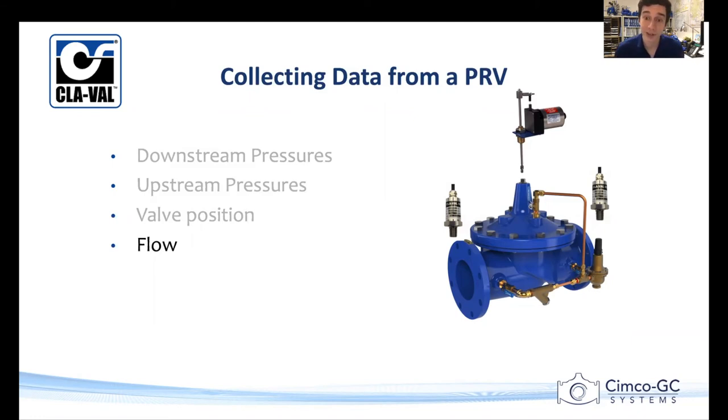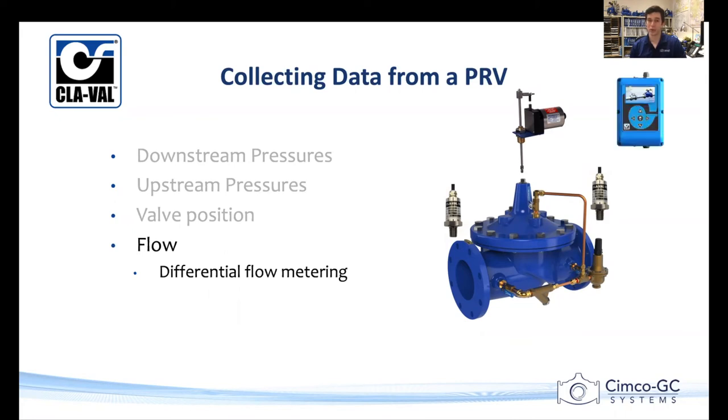flow. So pressure reducing valves, they just manipulate flow in order to maintain pressure, but it is really useful to know where water is going in our systems. So collecting flow at our pressure reducing stations is really, really useful. We can do that a couple different ways. One of the ways that we can do that is through differential flow metering. Differential flow metering is we're going to take these components right here and we're going to calculate what the flow is.